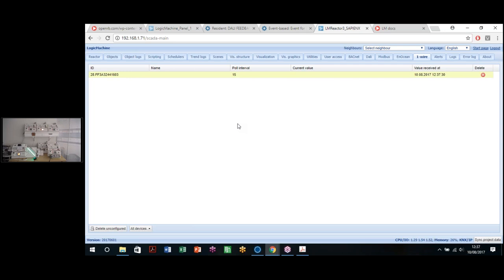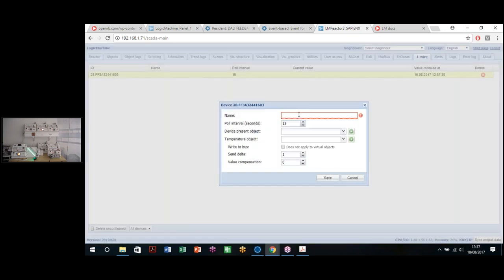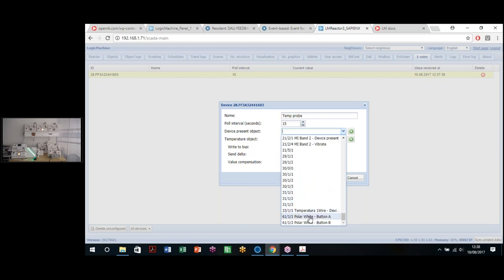There we go. There we have that it has detected a one-wire temperature sensor. It has a unique ID that we can use. Also, to configure this one-wire device, we are going to click on the device and set a name, temperature probe. We set, of course, a poll interval, because for this type of configuration we need to poll the devices. So it will ask us to set a present device object. This will tell if the device is present or not.